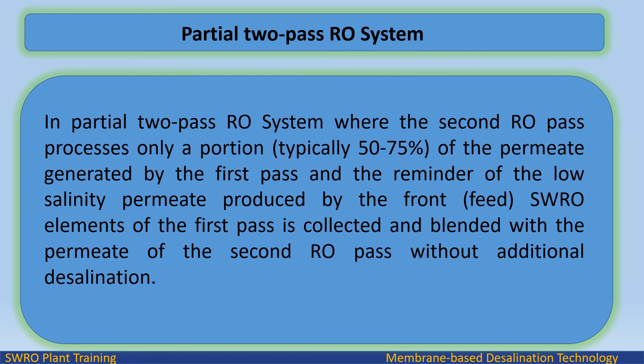In a partial two pass RO system, the second RO pass processes only a portion — typically 50 to 75% — of the permeate generated by the first pass. The remainder of the low salinity permeate produced by the front feed SWRO elements of the first pass is collected and blended with the permeate of the second RO pass without additional desalination.